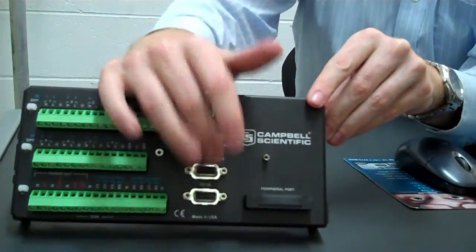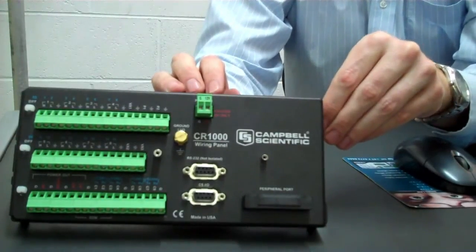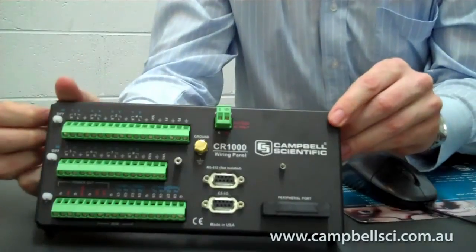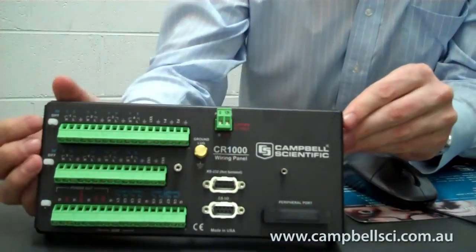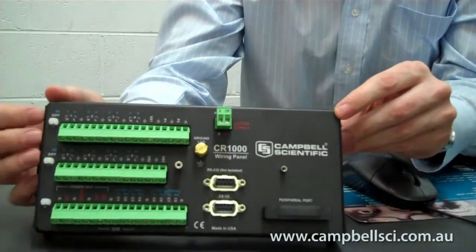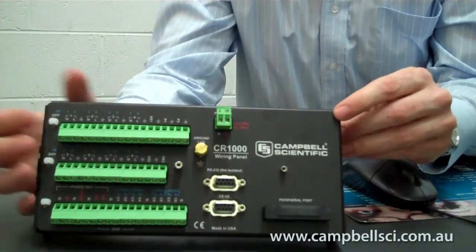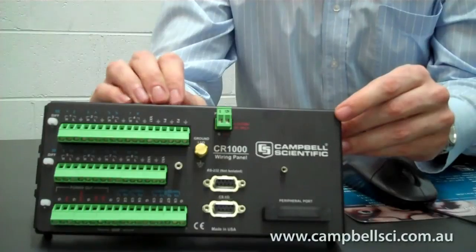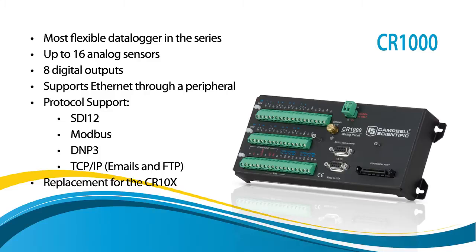Some of the other things on the wiring panel: over here we have two DB9 connectors — one for an RS-232 port and one for a CSIO port. The CSIO port is on a lot of our loggers; it stands for Campbell Scientific Input or Output, so that is to connect only Campbell devices — things like our landline modem, radio modems, and all sorts of Campbell peripherals. The RS-232 port is a standard RS-232 port; we use that to connect to laptops to download data or program the logger, or to connect to PLCs or RTUs. The CR-1000 supports DNP3 and Modbus if you're connecting to a PLC.